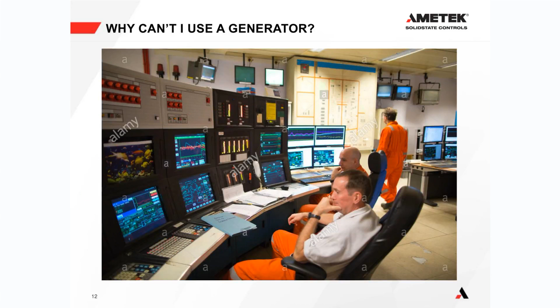You can't see what position the valves are in. You can't see what temperatures some of the critical pipes in the process are. And not just that - due to the DCS system not being able to control those pumps, solenoids, and other devices, those systems would go into a fail-safe mode, which usually means a controlled shutdown. Therefore you have to shut down the plant, which is extremely expensive.